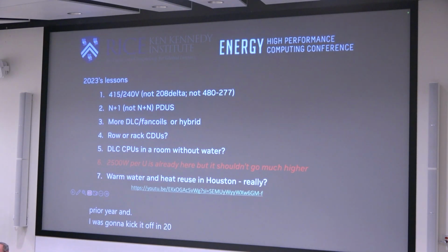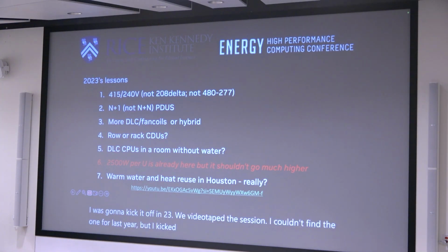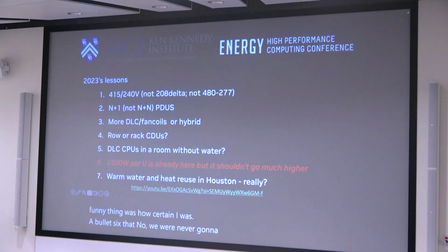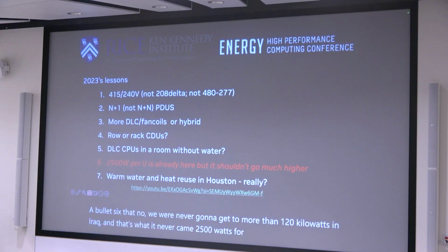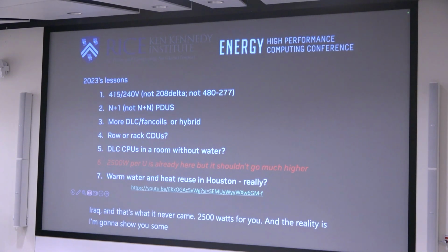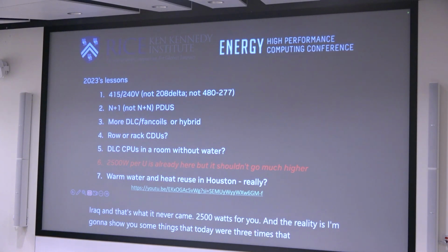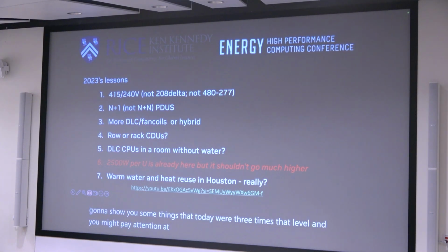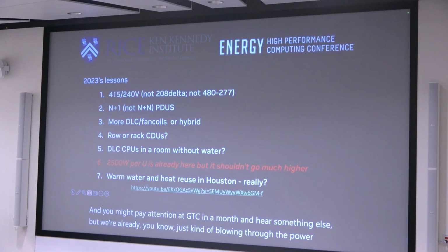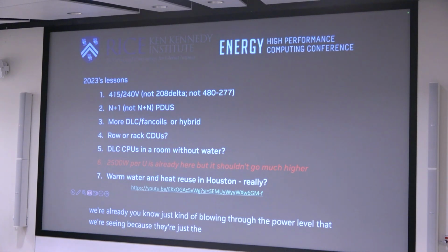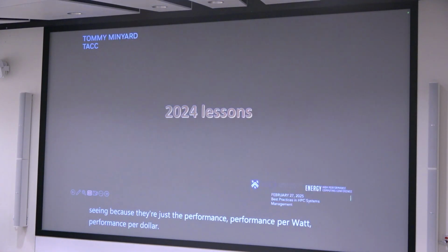Back in 23 we videotaped this session. I couldn't find the one from last year, but I kicked off with some of the comments. The funny thing was how certain I was that we were never going to get to more than 120 kilowatts in a rack, and that's where the number came from, 2,500 watts per U. The reality is I'm going to show you some things that today are three times that level. You might pay attention at GTC in a month and hear something else, but we're already blowing through the power level we expected, because the performance per watt, performance per dollar, is great.